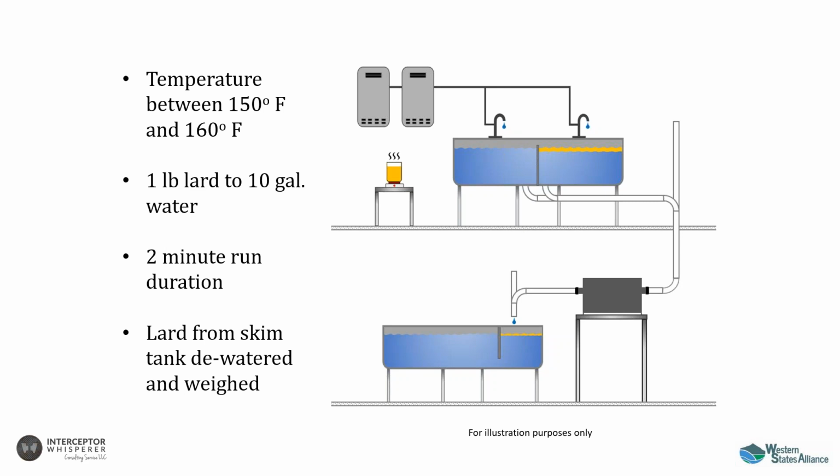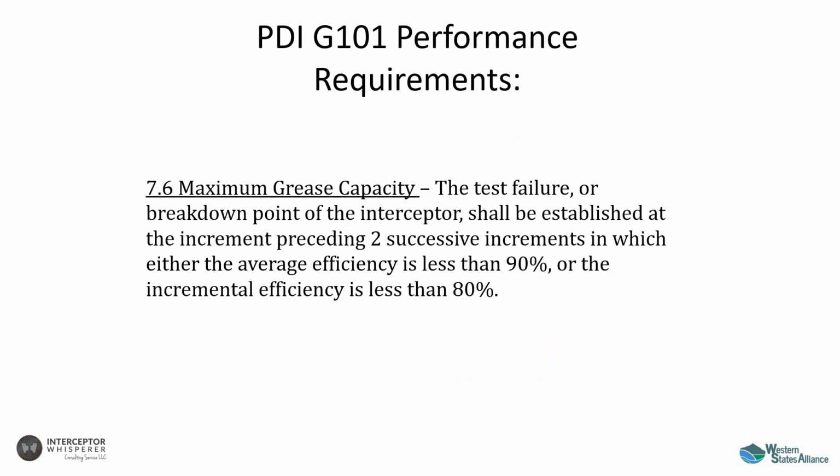Now, when it comes to the actual certification, this is where we begin to see some interesting things that have happened over the years. Up until about 2012, there was only this certification. You must test your grease interceptor to the maximum grease capacity. Legacy grease interceptors were always tested to their maximum capacity. But the motivation from the very beginning was a military installation in which maintenance wasn't really a question. You're going to have some privates told to clean out the grease interceptor at least once a day, or maybe more than once a day, and it wouldn't really matter. It's a military installation. They can do it as often as they need to.